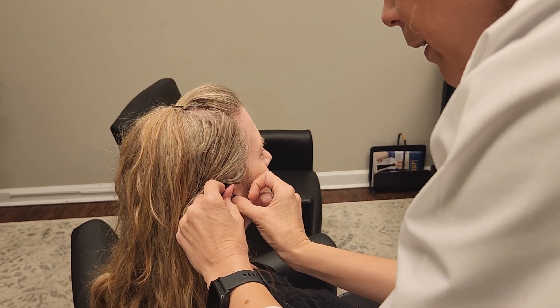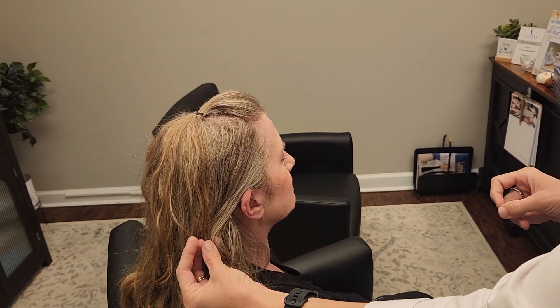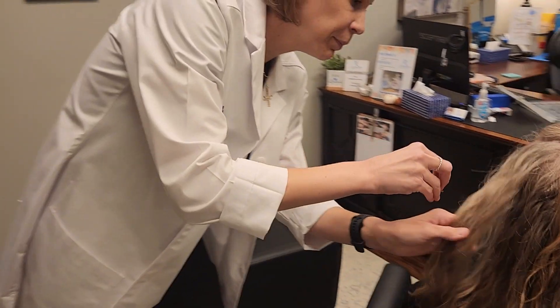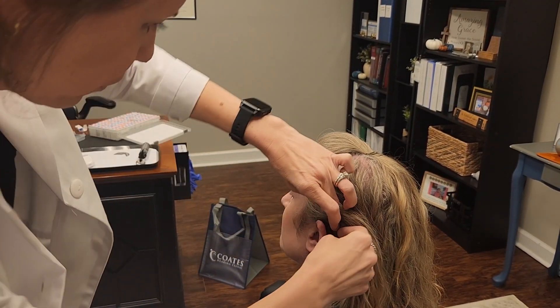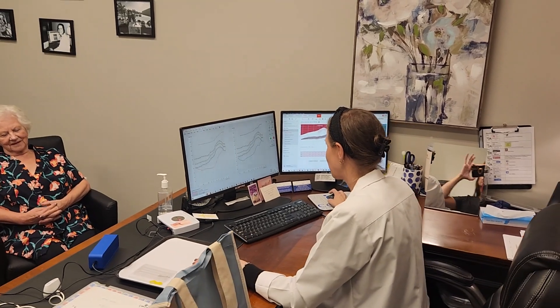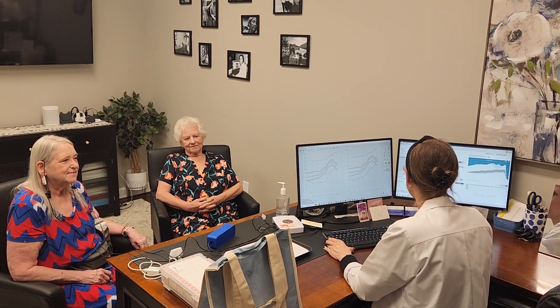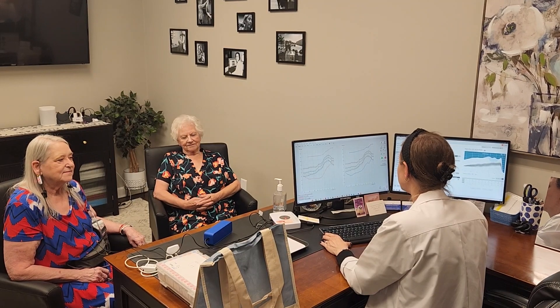That can be very difficult. The majority of patients are fit with behind-the-ear devices, or what we call receiver-in-the-canal, which requires a measurement of wire length as well. There are about five different wire lengths to determine a secure fit. Some patients require different tips and wire lengths between the ears — we are all a little asymmetrical. After the physical fit, next up is the calibration testing. The benefits of these tests include reducing the risk of microphone feedback, or the whistling sound that hearing aids used to have, and ensuring the patient is receiving the right amount of amplification at each pitch or frequency based on the hearing test.